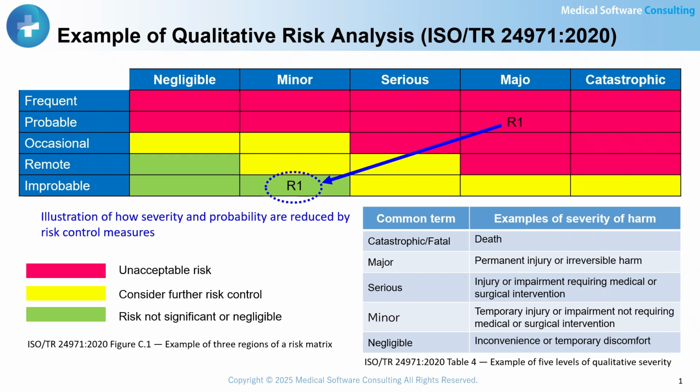This analysis evaluates whether the expected benefits of the intended use of the medical device outweigh the residual risk. It is important to note that benefit risk analysis must not be used to justify residual risks by comparing them with business or economic benefits.